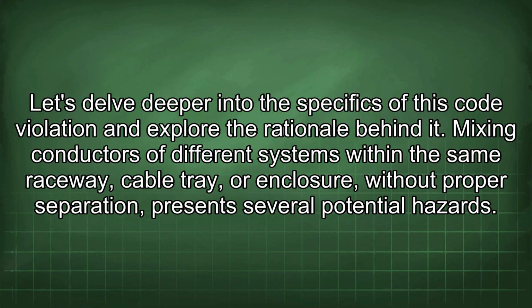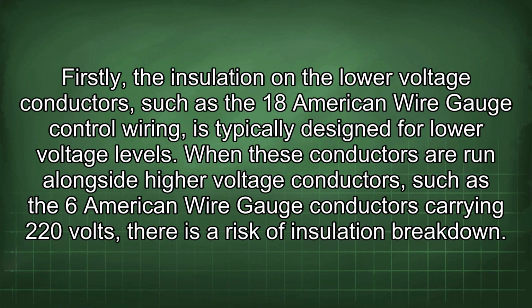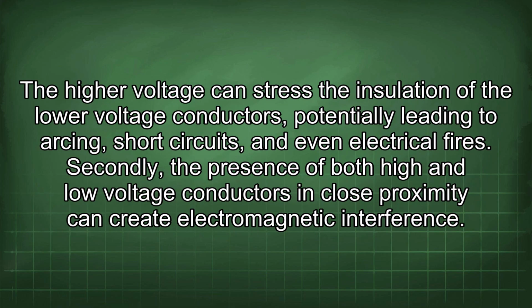Let's delve deeper into the specifics of this code violation and explore the rationale behind it. Mixing conductors of different systems within the same raceway, cable tray, or enclosure without proper separation presents several potential hazards. Firstly, the insulation on the lower voltage conductors, such as the 18 American wire gauge control wiring, is typically designed for lower voltage levels. When these conductors are run alongside higher voltage conductors, such as the 6 American wire gauge conductors carrying 220 volts, there is a risk of insulation breakdown.